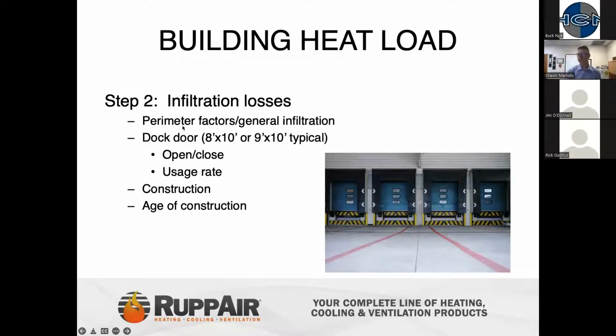Again, what are the ventilation requirements? What are the code requirements? But more importantly, what happens when dock doors open? What happens when dock doors are facing a west wall rather than an east wall? What are the construction characteristics that may impact this infiltration rate? And what's the age of the building? The biggest thing we see now is that these new buildings are a very, very tight construction. So the biggest thing with that tight construction is that if you're bringing heated air into the building to meet the ventilation rates, that air needs to get back out as well. So we're going to talk more about that.